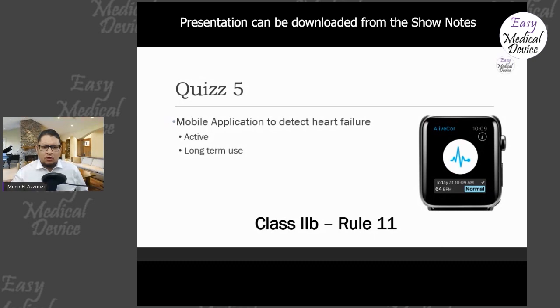It says if it's a death or irreversible deterioration of the person, then it's class 3. If it is a serious deterioration of the person or of health, or a surgical intervention, then it's a class 2B. If it's intended to monitor a physiological process, it's classified as class 2A, except if it's a monitoring of a vital physiological parameter, then with an immediate danger for the patient, which is then class 2B. And for all the other cases, it's class 1. So you see that there is a graduation of things where you have really to define what is the intended purpose of your device.